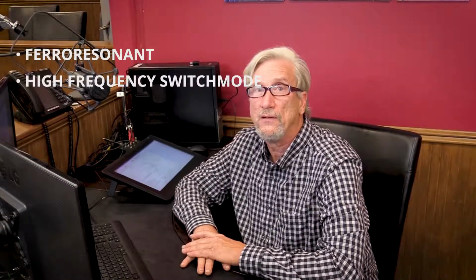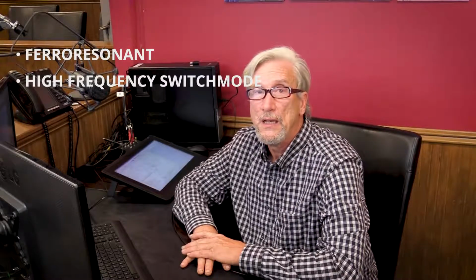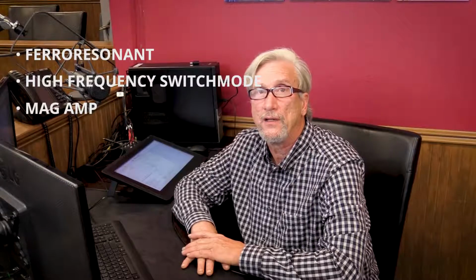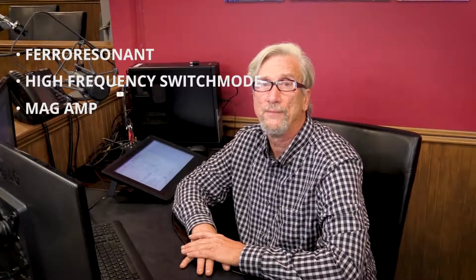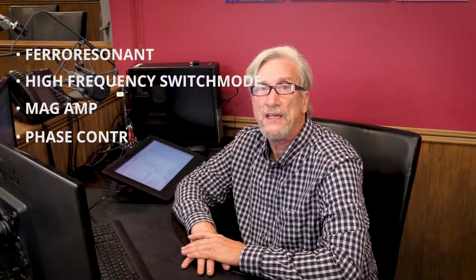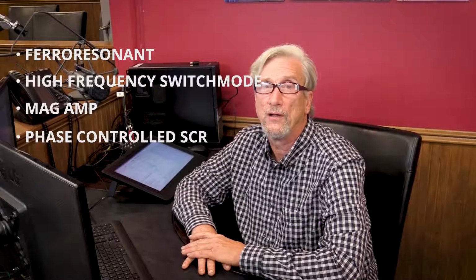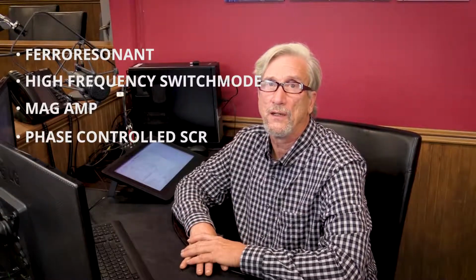I'm talking about topologies for the stationary battery charger. There are really four main commercial topologies. The first is a ferro-resonant, controlled ferro, which uses a particular piece of magnetics to control the output. The next is high-frequency switching, which is done a lot in telecom work. There's a mag amp, which uses an inductor controlled in front of the transformer. And the last is the phase controlled output using SCRs. In this broadcast we're going to talk a lot about that last topology, where we're using SCRs and controlling when they're being turned on.